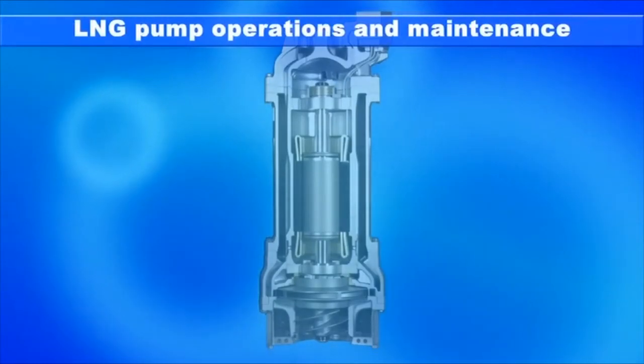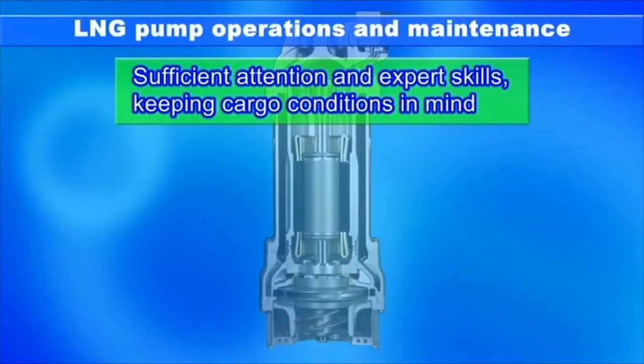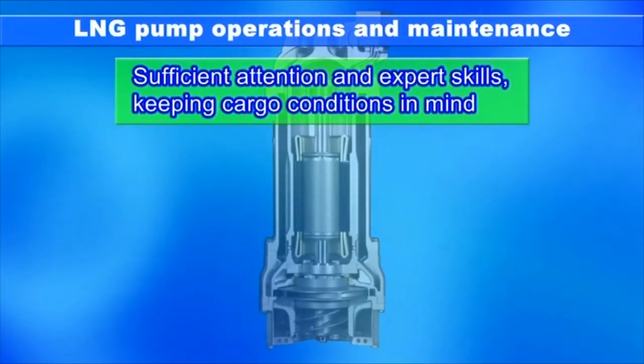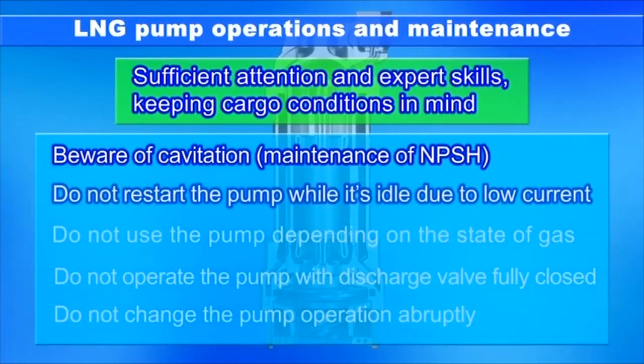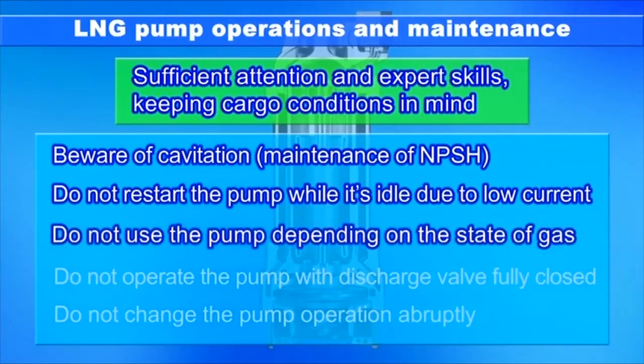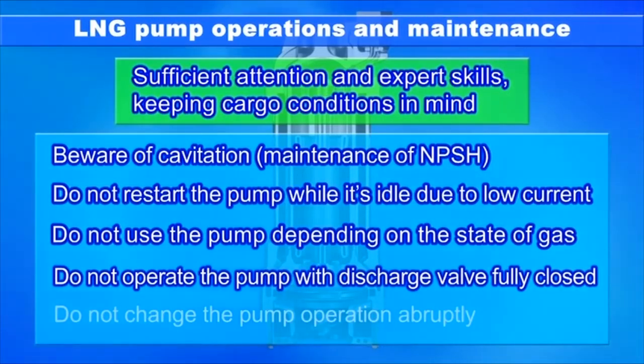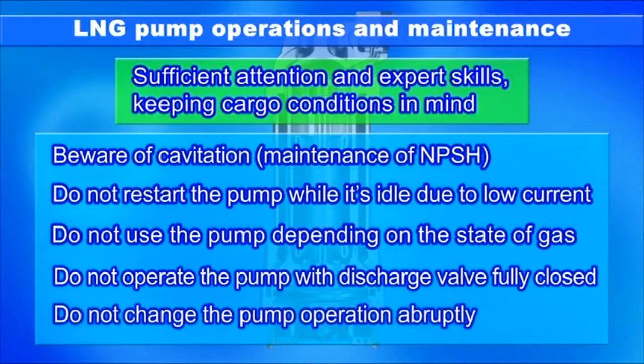To operate LNG pumps, sufficient attention and expert skills are indispensable while keeping cargo conditions in mind. Points to consider are: beware of cavitation, the maintenance of proper NPSH, do not restart the pump while it's idle due to low current, do not use the pump depending on the state of gas, do not operate the pump with the discharge valve fully closed, and do not change pump operation abruptly.